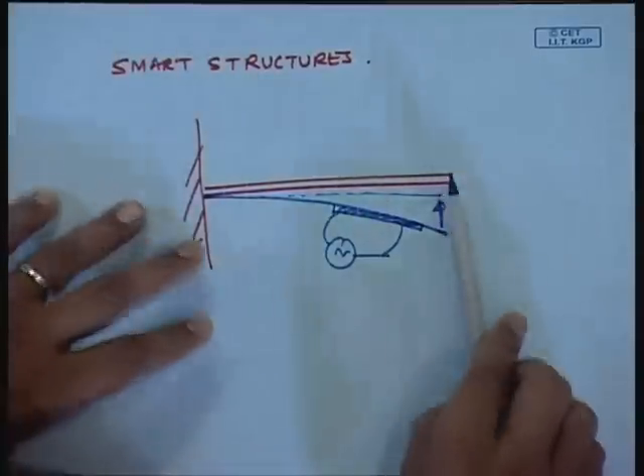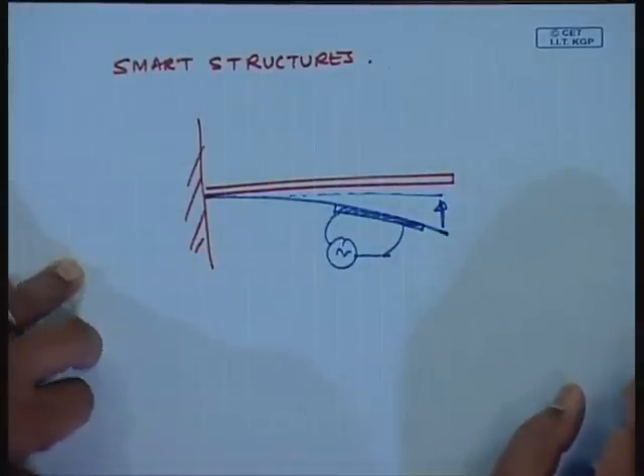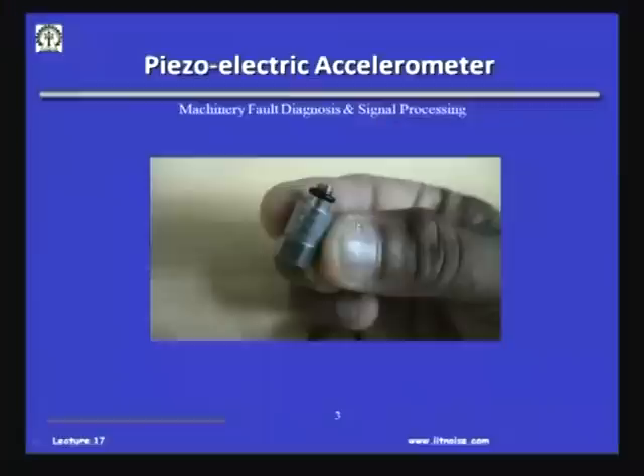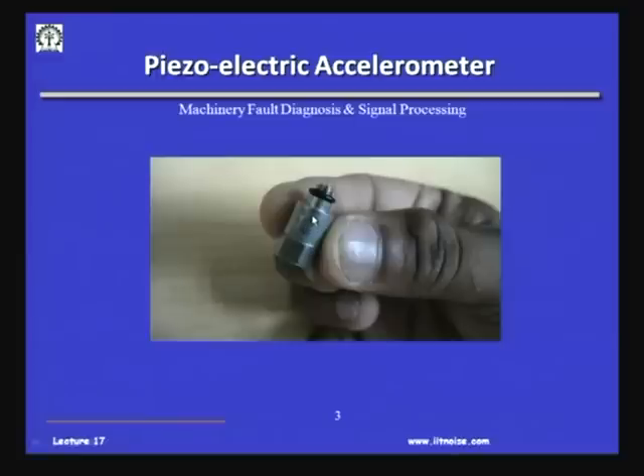We are not going to discuss smart structures in the transducers for CBM context, but it suffices to say that in accelerometers nowadays, we use piezoelectric crystals as the sensing elements because they can withstand high temperature, do not require an external power supply like a strain gauge, and can be made very small. For example, looking at this accelerometer, this is the connector wherein we get the charge signal, which will be amplified and propagated. The piezoelectric crystal is already sealed inside the casing.